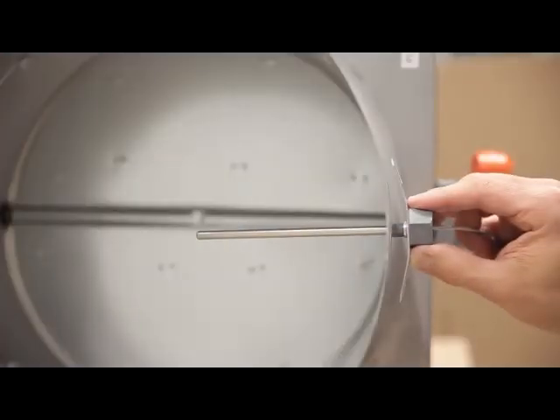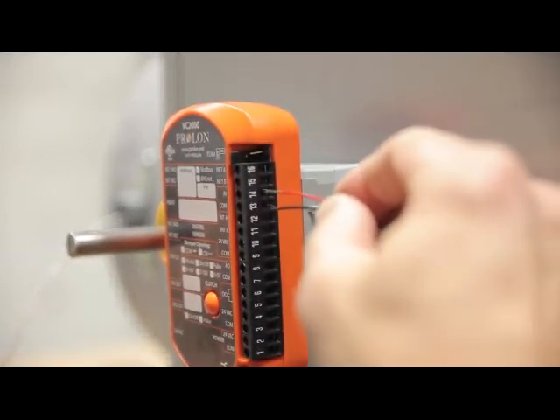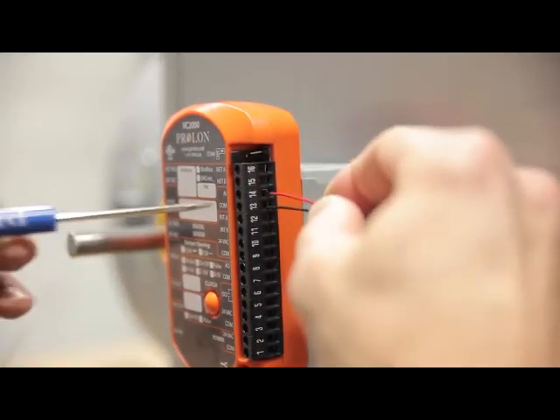Install the duct temperature sensor at the box's inlet. Now wire the duct sensor to the analog input on terminals 13 and 14.